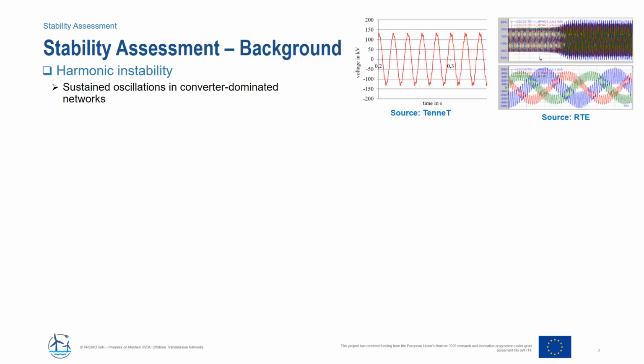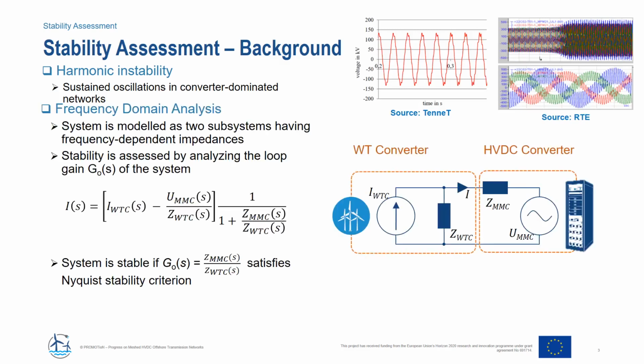The background of this assessment is that, as we know, with the increased penetration of power electronic devices, they have introduced a new category of instability. That's harmonic instability, the sustained oscillation in such converter-dominated networks. This is going to be shown in the diagram to the right. Here in this analysis, we use frequency domain analysis to address this instability. For example, in this diagram, with a wind turbine converter connected with an HVDC converter, we model the system as two subsystems having frequency dependent impedance and also the corresponding current source and voltage source.